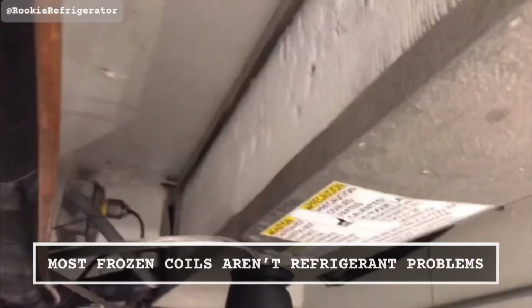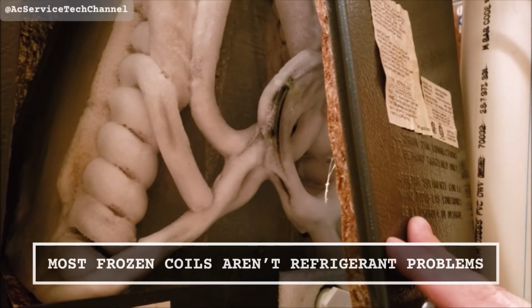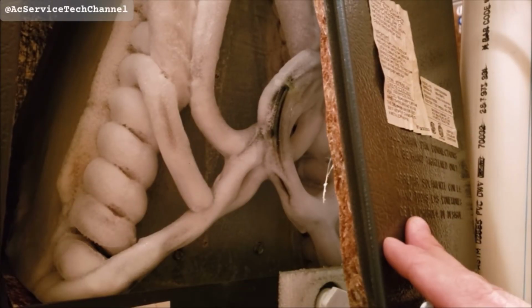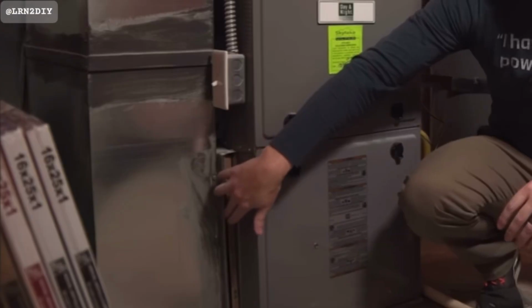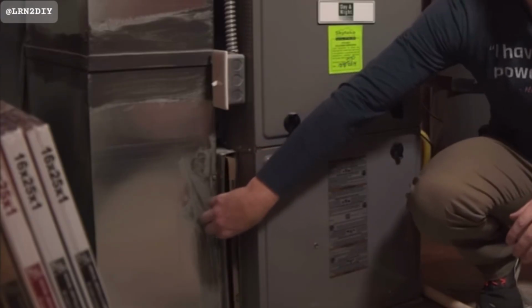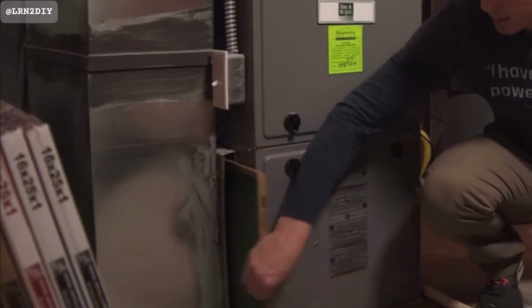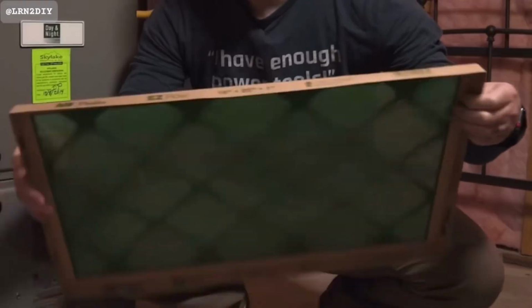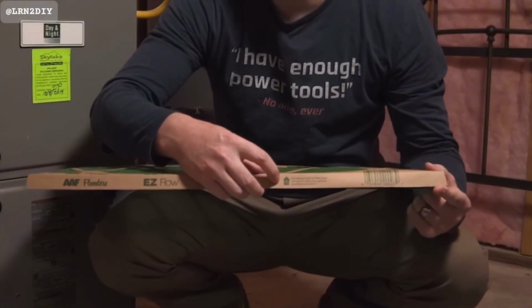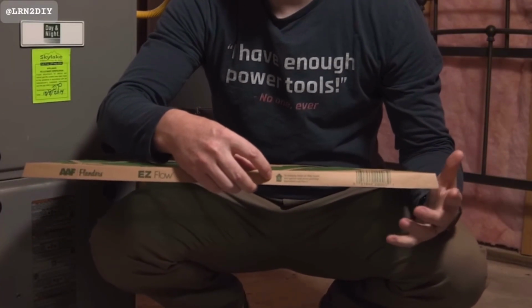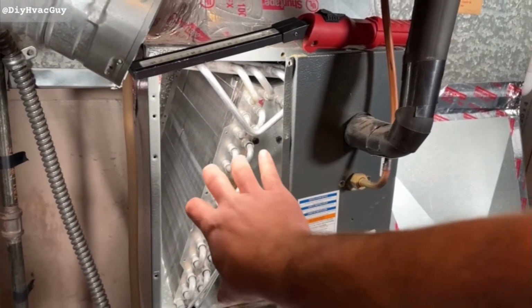Number 5. The AC freeze misdiagnosis ladder. When your evaporator coil ices over, the cause is almost never low refrigerant first. The order of likelihood, from what I see on the routes I cover, runs about 70% dirty filter, 20% restricted airflow somewhere else like a kinked flex duct or a closed register, and 10% actual refrigerant issue.